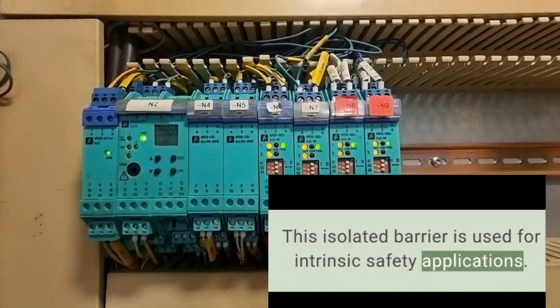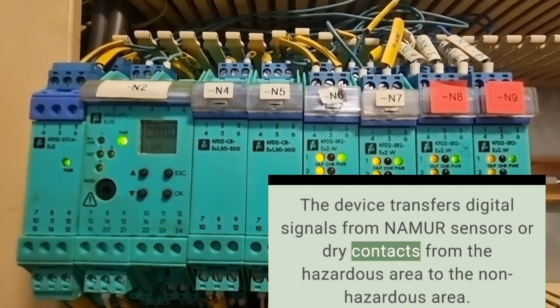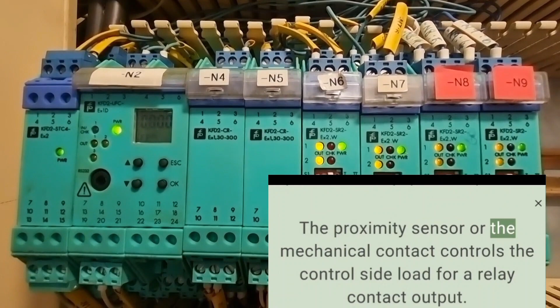This isolated barrier is used for intrinsic safety applications. The device transfers digital signals from NAMUR sensors or dry contacts from the hazardous area to the non-hazardous area. The proximity sensor or the mechanical contact controls the control side load via a relay contact output.